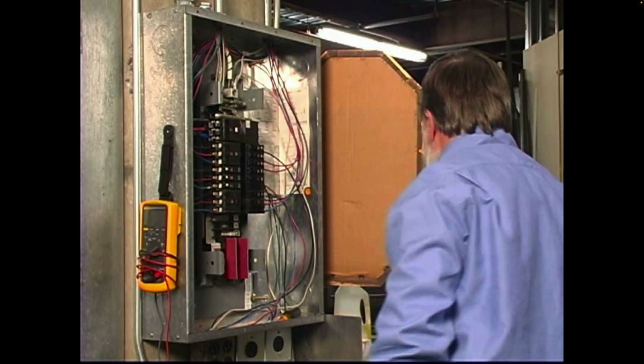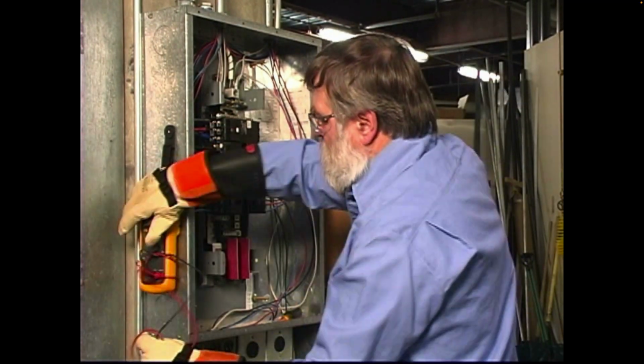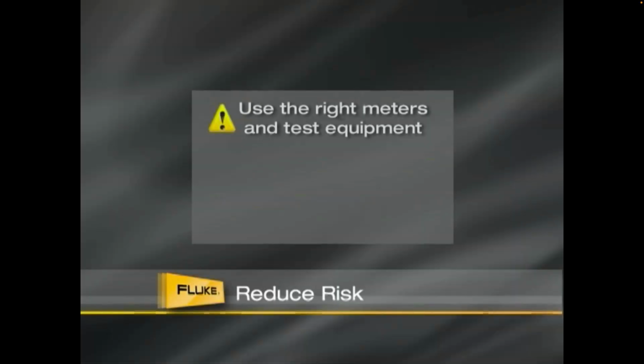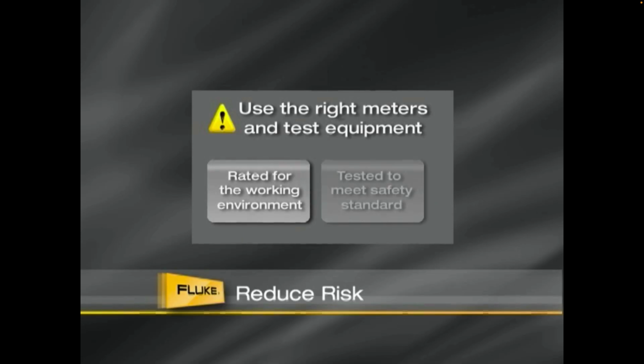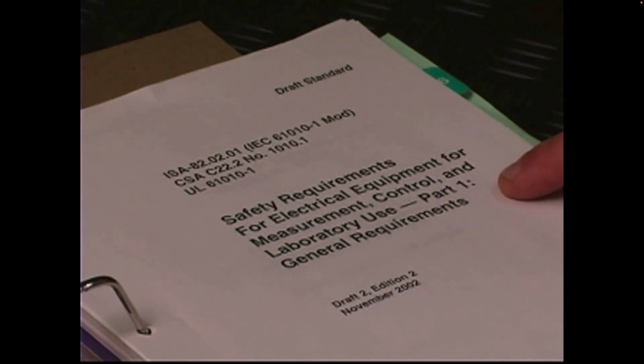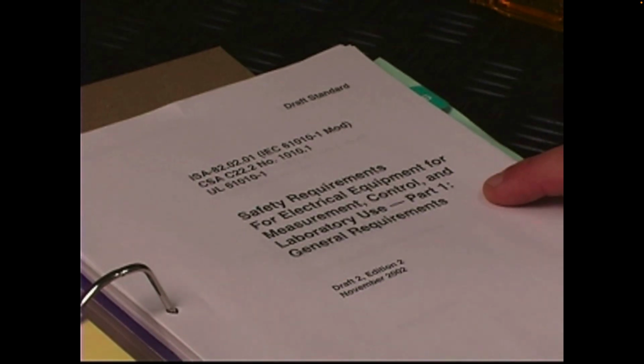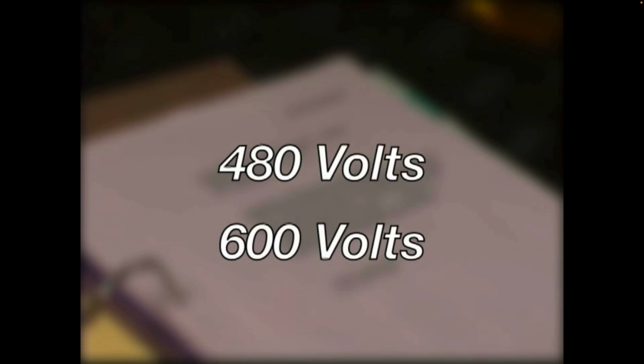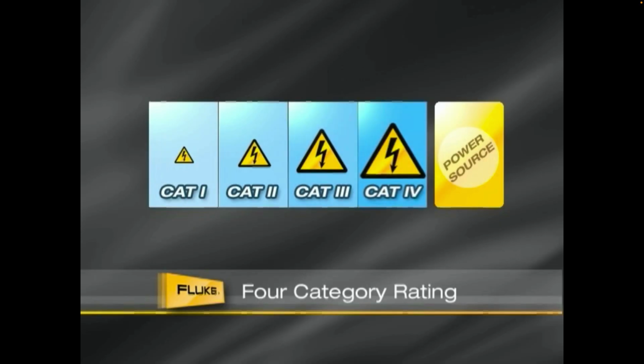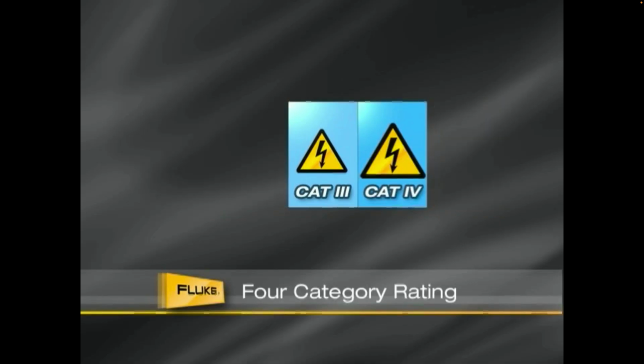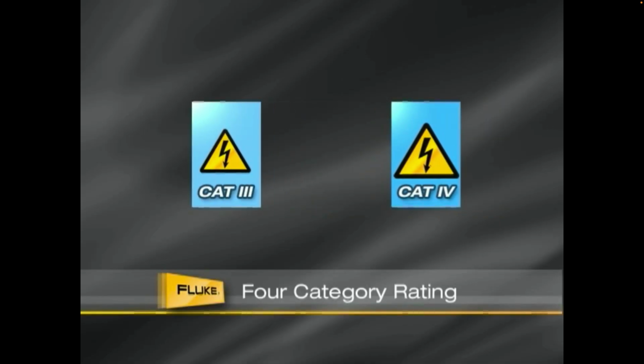In these circumstances, proper procedures alone are not enough. You need to reduce risks by using the right meters and test equipment, tools rated for the environment where you're working, and tested to meet the appropriate safety standards. To provide better protection for electrical workers, new standards have been developed for test equipment used in environments of 1,000 volts or less, including 480 volt and 600 volt three-phase circuits. In the 4-category rating system, the closer you are to the power source, the higher the category, and the greater the danger. Transients in categories, or CATs 3 and 4, can be extremely dangerous.